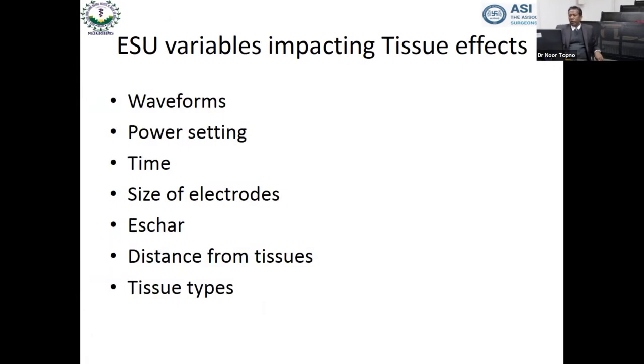Now, the electrosurgical unit has various variables on which the tissue effects depend. One is the kind of waveform which I had talked about initially, and the power setting. We keep saying increase the power because it is not cutting enough or not coagulating enough. Then the time duration for which we are using the active electrode on the part that we wish to cut or coagulate. And also the size of the active electrode which we are using, whether it's a small surface or a large surface, and how much eschar formation has happened on the electrode.